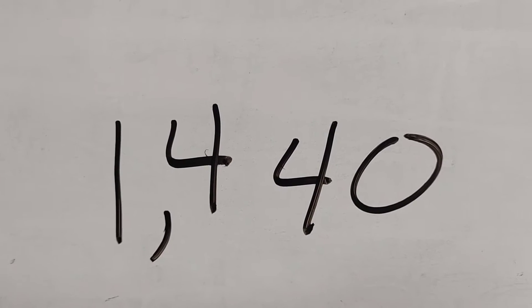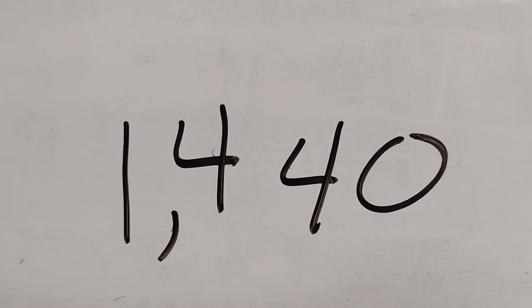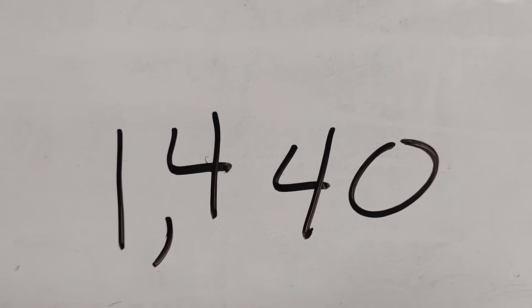It's important to note when calculating something like this that you don't want to just calculate what you are using. If you're putting in standard incandescent light bulbs, for example, you might be thinking, 'I'm only going to have a 65 watt light bulb in there, so I'm good.' But other people might end up using a 75 or even a 100 watt light bulb in that exact same fixture. So the number you want to use for calculating the wattage is the rating of the fixture you are using.